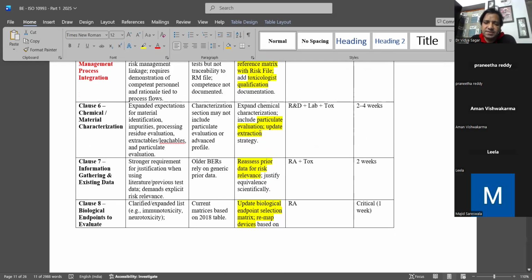Particulate size: start working on the particulate matter on your devices. There are different ways to measure particulate matter, and it is difficult on the device itself, but you can do a simple immersion test: a total immersion of the device in some solvent, organic or inorganic. Then all your particulate matter will come down. Then you need to filter it using 0.03 micron or 0.02 micron filter papers. Then you'll get everything in a vacuum oven. Then there is equipment which directly gives you an automated particle count and size.